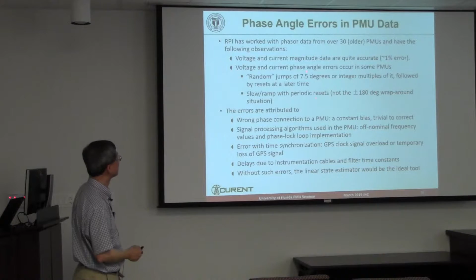The idea is actually very simple. All the PMUs are connected with what we call redundancy. This is a redundant bus—it doesn't have a PMU, but it can be observed and calculated from this end, since it has a voltage and current measurement. It can also be calculated from another bus using its voltage and current. So you can calculate this bus from two different sources.